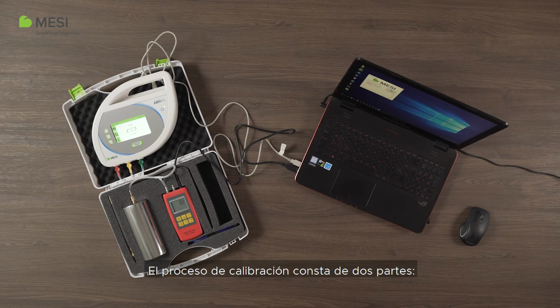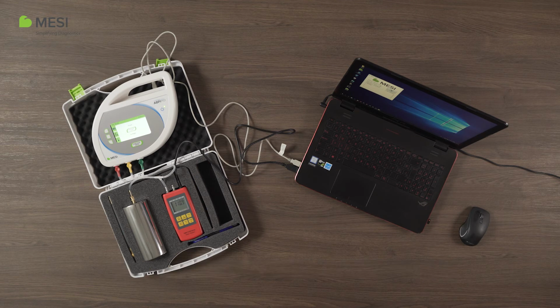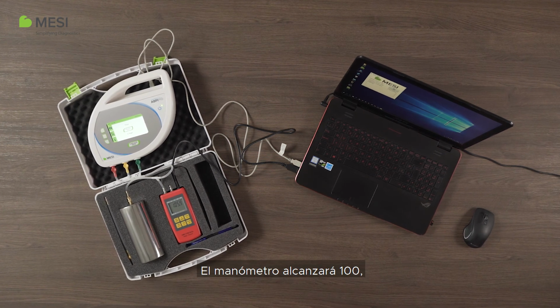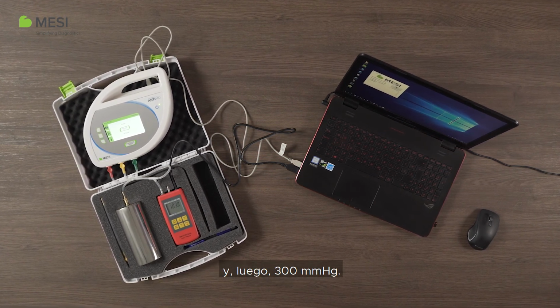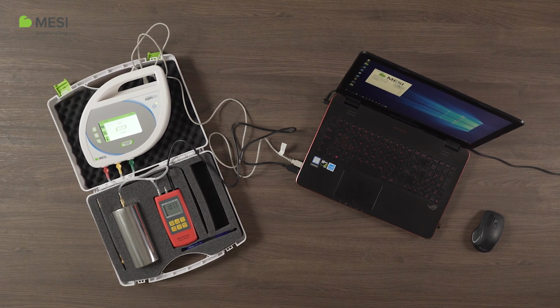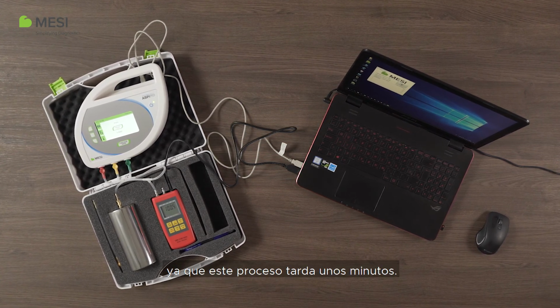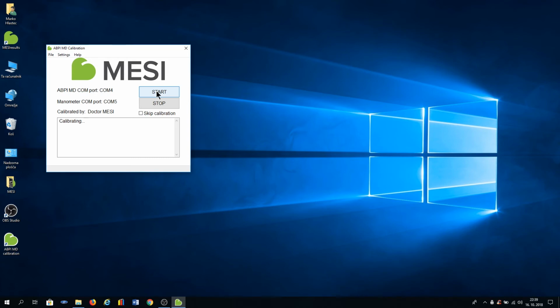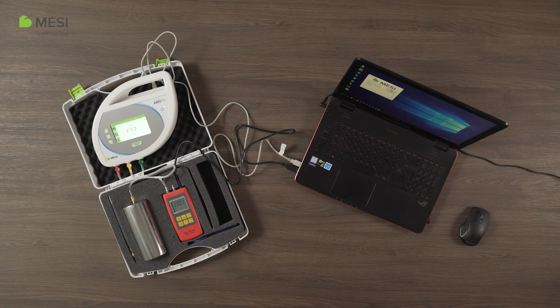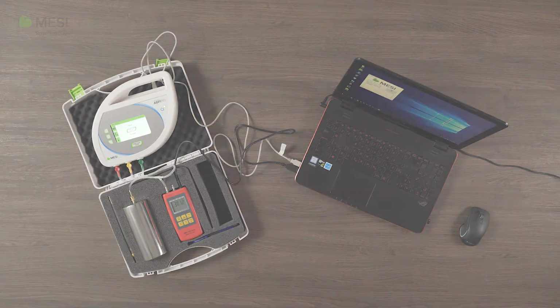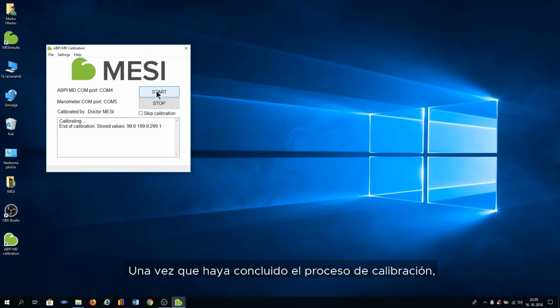The calibration process consists of two parts: the calibration and measuring the pressure for the calibration certificate. Part 1. Calibration. The manometer will reach 100, then 200, then 300 millimeters of mercury. Be patient, this process takes a few minutes. After the calibration process is concluded, the pressure measurement for the calibration certificate will start automatically.